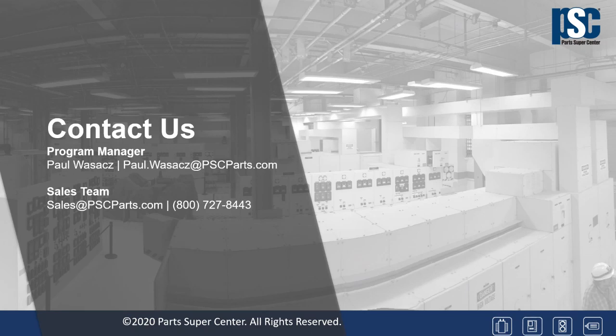What we would recommend if a customer has a large number of primary disconnects in service would be to create a program to change them out and have them remanufactured. When we remanufacture them, we break the porcelains out of the metal bases. We test the metal bases to make sure there's no cracks. We then cement in new porcelains. And the reason we put new porcelains in is because there is no easy way to test the porcelains for cracks. It's very difficult to hydrostatically test those porcelains without taking them out of the metal base and without removing the babbited in copper contact. So that's the reason why we replace the porcelains.